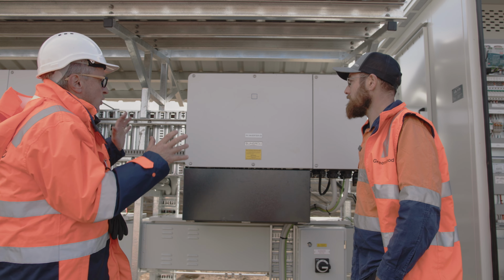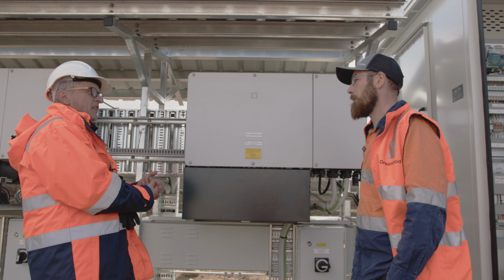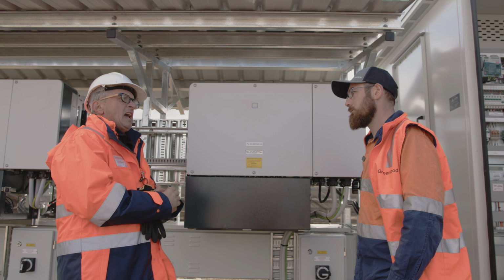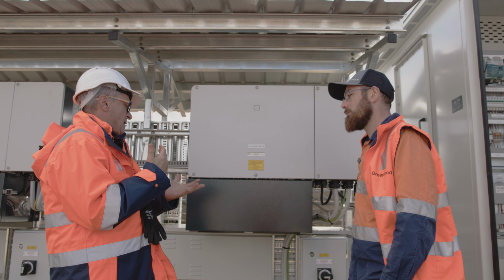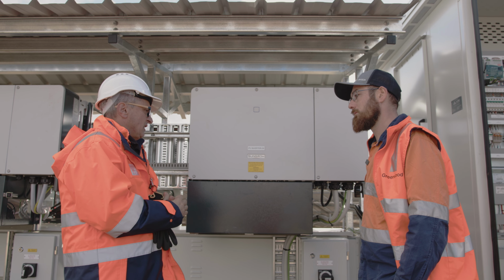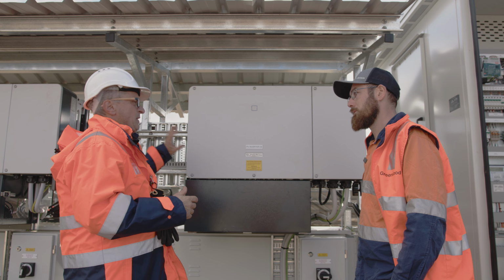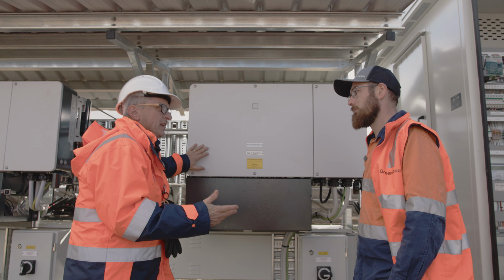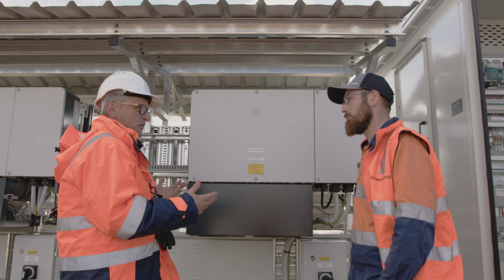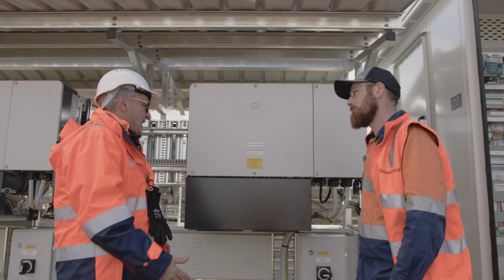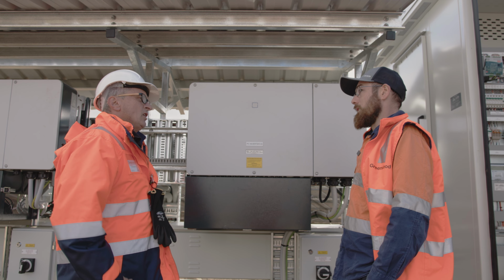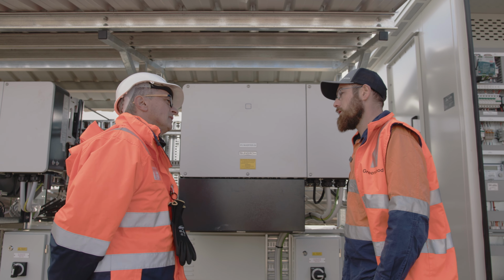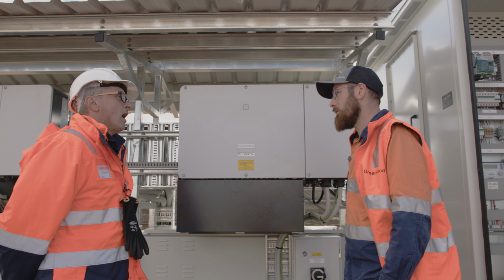Now, we haven't talked much about the voltage of the string. There are 18 panels, and I did a quick VOC max calc - it would go over the capacity if you put 20 in the string, but with 18 you're talking up around 850, 900 volts, aren't you? Yeah, so when we tested these strings, most of them came in at about 930.